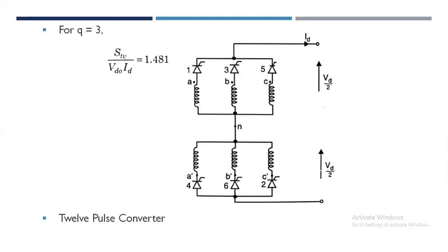The use of a 12 pulse converter is preferable over the 6 pulse converter because of reduced filtering requirements. However, increasing the pulse number beyond 12 is not practical because the non-characteristic harmonics, which arise due to asymmetry in firing, imbalance in supply, etc., are not eliminated.